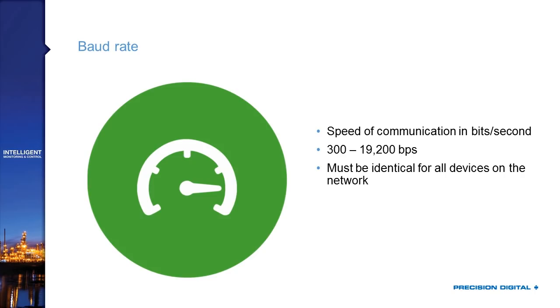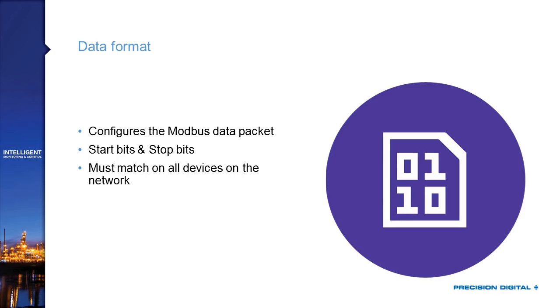Data format tells devices what form data is arriving in — for example, how many start bits and stop bits are used, and whether the data is an integer, long, or floating point. So long as all your devices are properly matched on data format, you don't need a deep understanding of it. If a device says it has one stop bit, make sure all your other devices are programmed with one stop bit. As long as you match all data format values, the system will operate just fine.